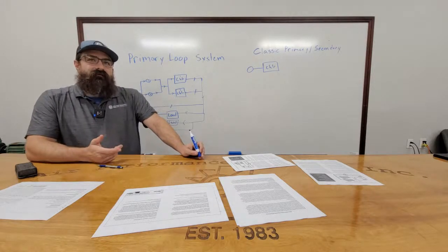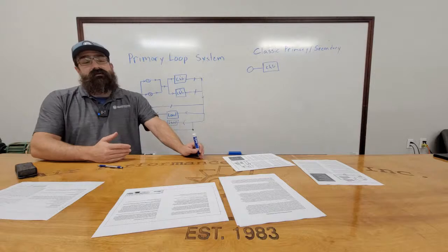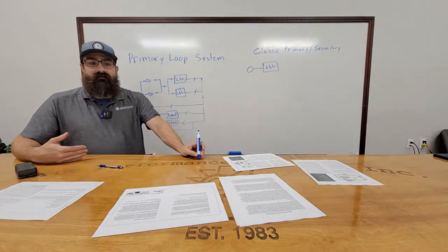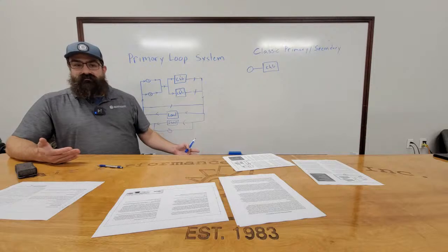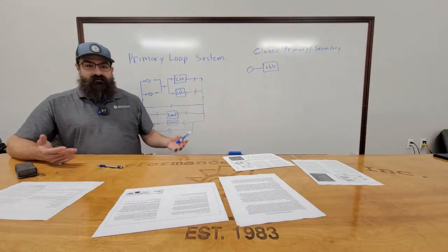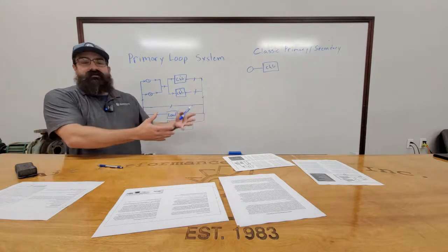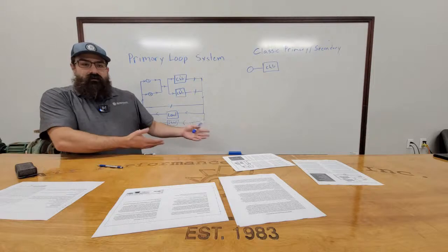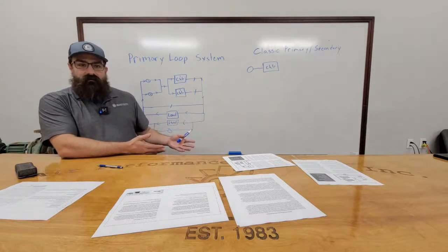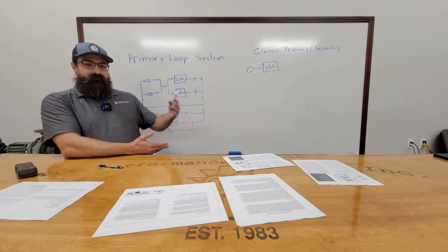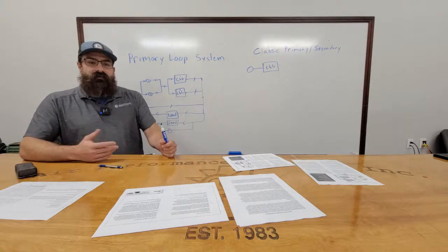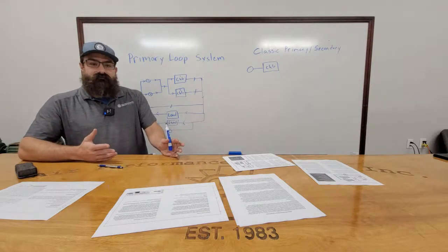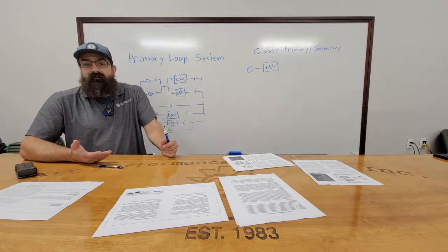Yeah, the building I'm referencing, the issue is they've come back and put so many fan coils in after the fact, and your trunk piping has not changed size, right? So you're limited on flow because you have an 8-inch pipe that serves the entire building. Well, it can only do 8 inches worth of flow. So the only way to get more differential for what the air handlers need is to run both pumps, right? You build pressure instead of flow because really you're limited on flow, right?